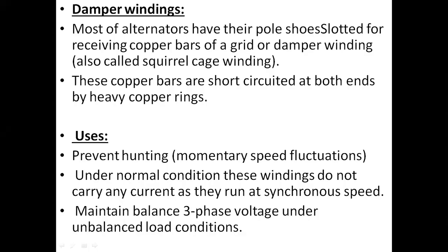Okay, so in order to prevent the hunting, we are using the damper windings. Actually, in generators, these are needed when synchronous motors have to provide high torques. So these turbo generators do not have damper windings, except in special cases. If you want to synchronize them, then we have to take the damper windings.